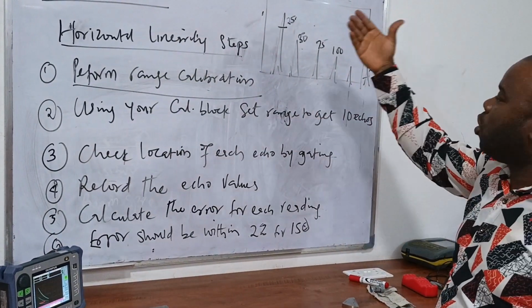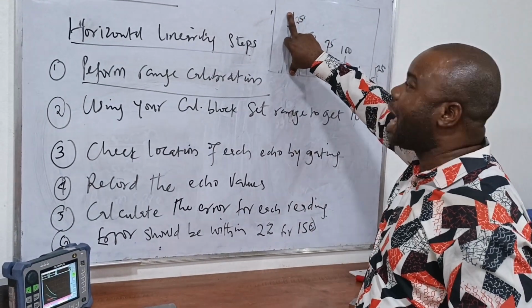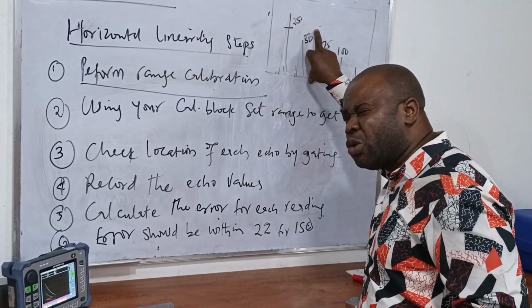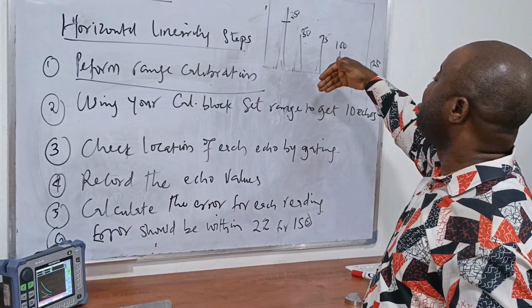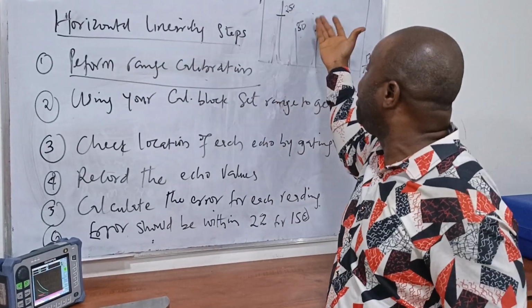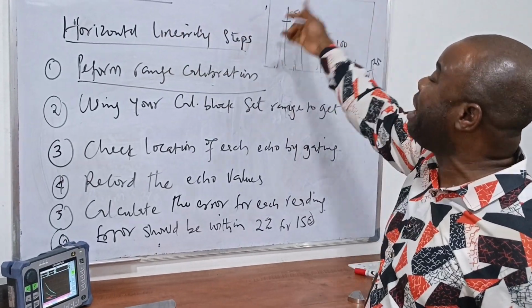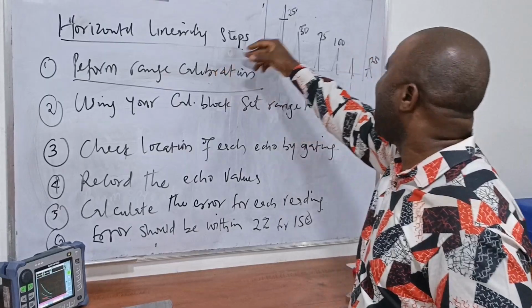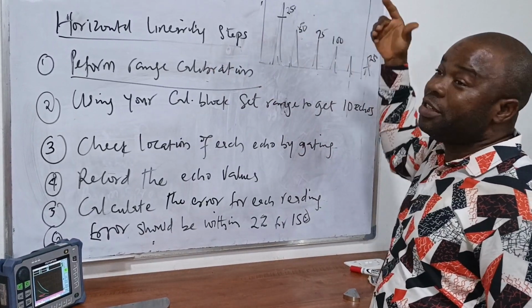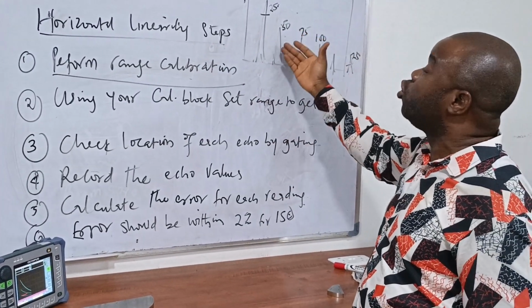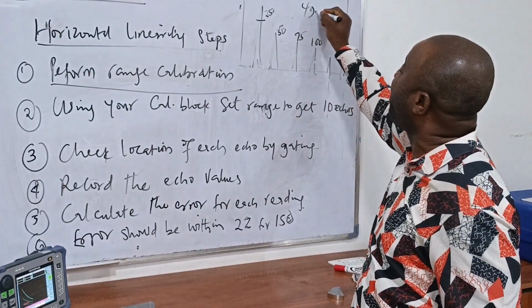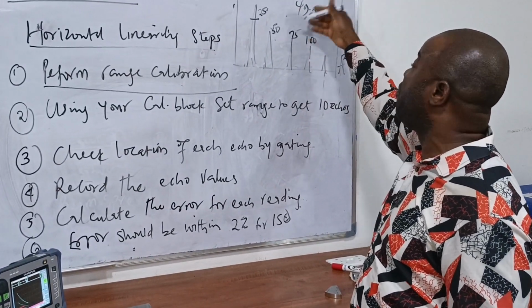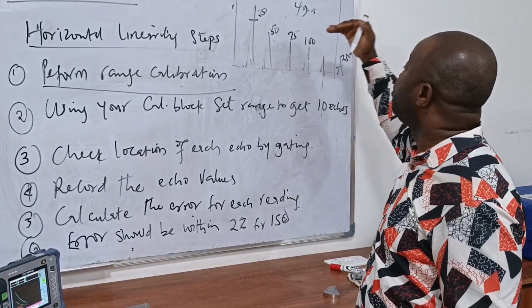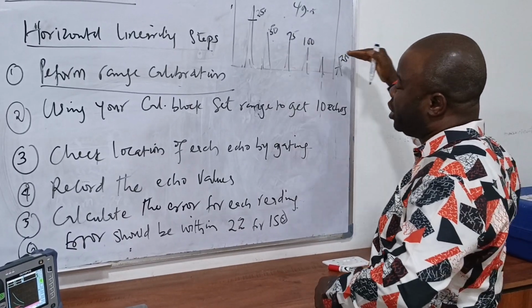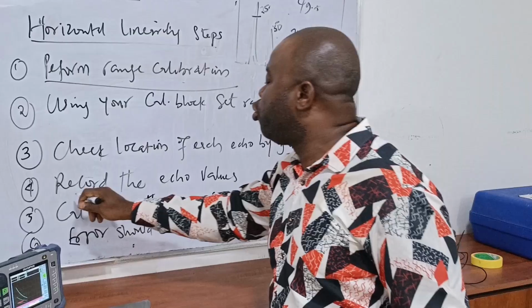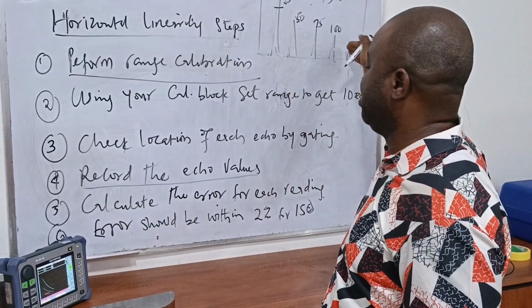What the linearity check does is this. If I check my first one, I get 25. I check my second one. If the equipment linearity is accurate, I should be getting 50. But in reality, most times we will not get 50. So maybe you get 49.5 or 49.2 or 50.1 or 50.2. You keep getting the variation as you check, so you need to record these values that you are getting.